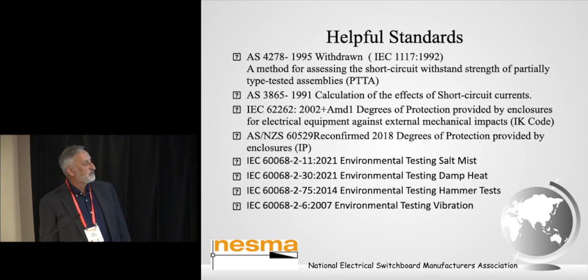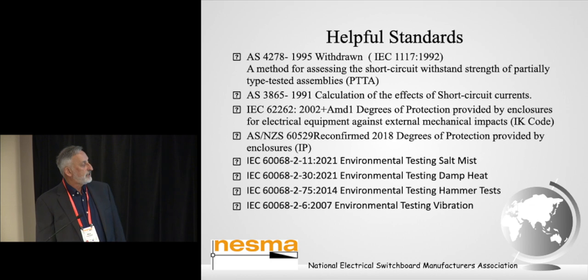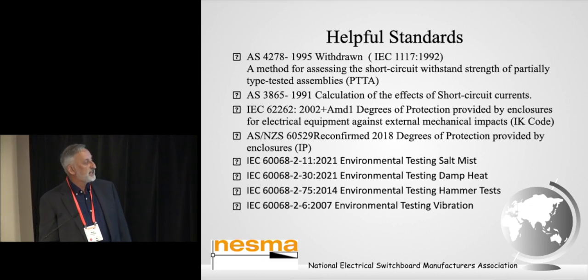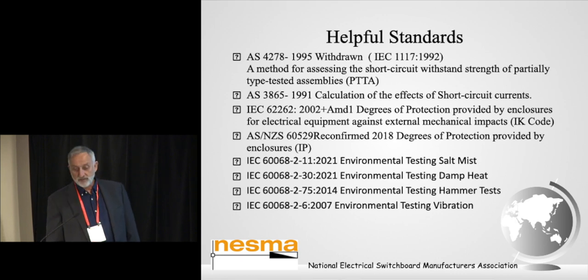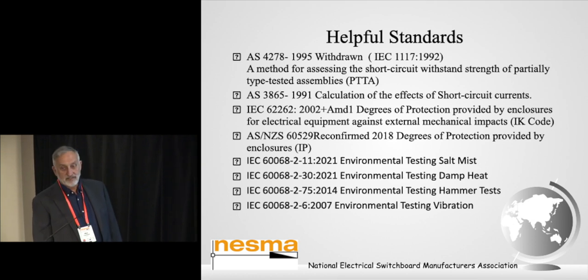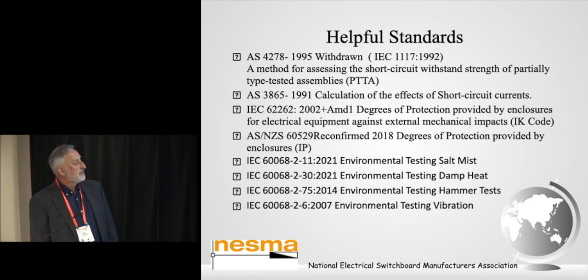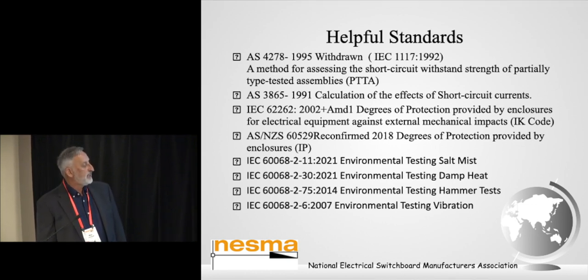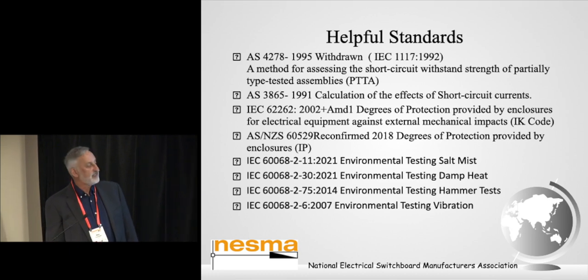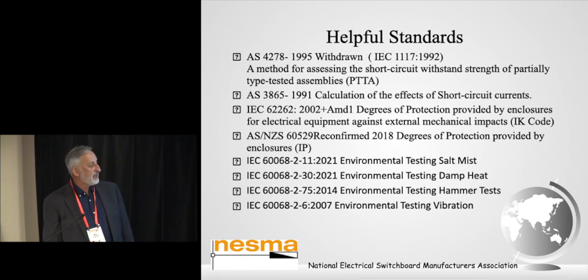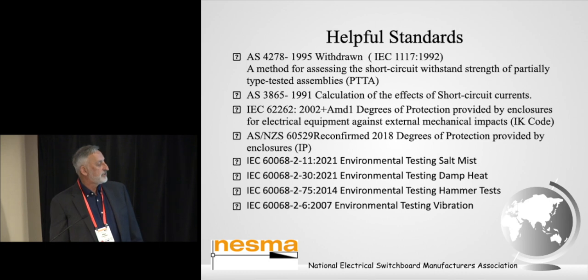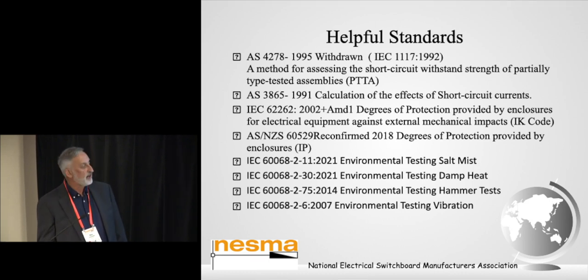3865, calculation of the effects of short circuits. IEC 62262, degrees of protection provided by enclosures against external mechanical impacts. And then the 60529, which is reconfirmed and under interrogation, the EL-026 committee has just been reformed, and they're looking at adopting the latest 60529 for IP enclosures. We have a series of the 68 series, 211, environmental testing, the salt mist and the damp heat. They're used for the corrosion test. The 275, the hammer test for impact, and the 26, environmental testing for vibration.